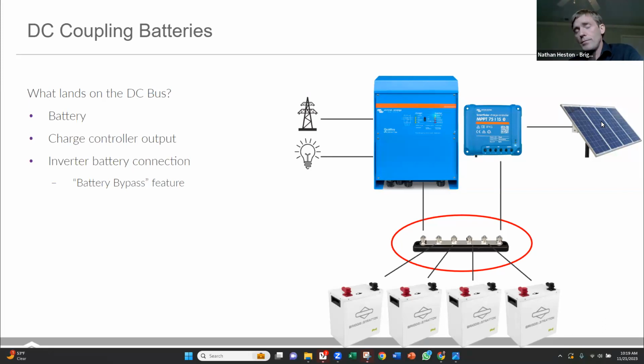Anytime you're drawing or pushing large amounts of current through a cable, battery cabling, you lose a little bit of voltage, right? That small amount of voltage over time can cause different loads on individual batteries. And so it's important we use equal cable lengths and keep those batteries balanced. That way, one battery is not stressed more than the others or charged more than the others. This power out of the solar or out of the battery bank is then pulled in through an inverter and can go out to grid or can go to power the loads. It's important to use a single battery bank, even if you have multiple paralleled inverters, etc. So keep that in mind as you're designing systems.